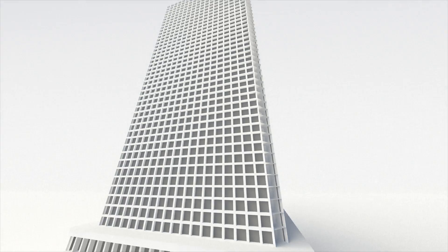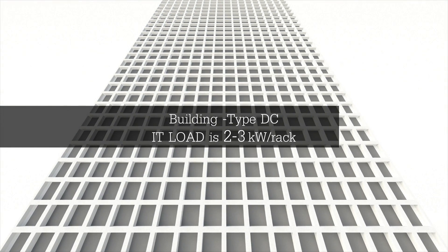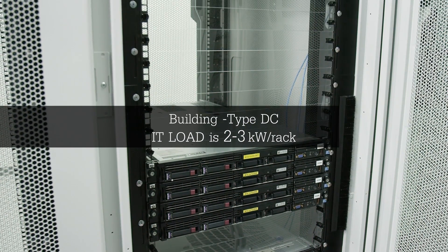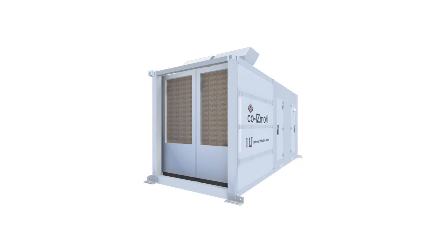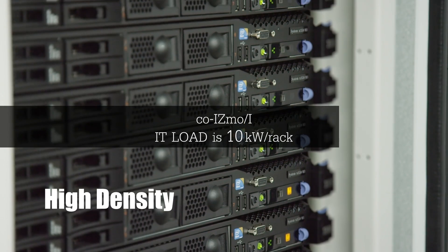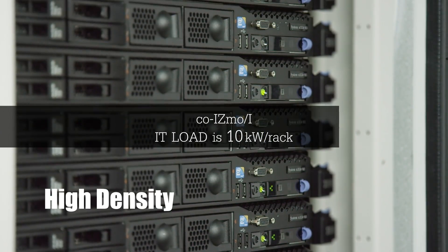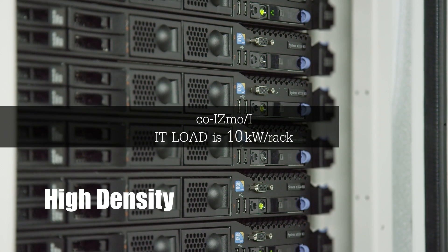Typical building type data centers provide 2-3 kilowatt IT load per rack. co-IZmo/I provides 10 kilowatt per IT rack. This high-density IT load not only increases IT rack space efficiency, it opens doors towards high-performance computing such as big data.